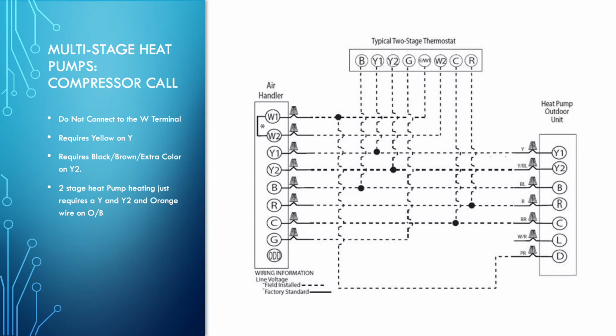So the very first thing we want to point out, when it comes to heat pumps with electric air handlers that have an electric backup heat kit, you do not put a wire on W at the thermostat. Don't use that. That is only for gas furnaces. Heating is created with a combination of your OB contact and your compressor call, which is on Y. Two-stage heating just requires a Y1 and a Y2 and a wire on OB. Now, we're not talking about the heat kit. We're just talking about the heat pump providing the first and second stage heating.